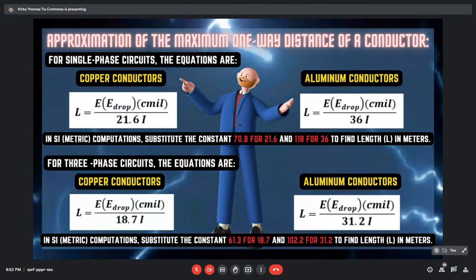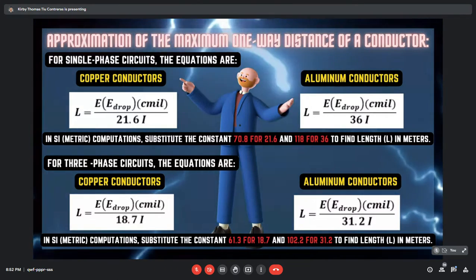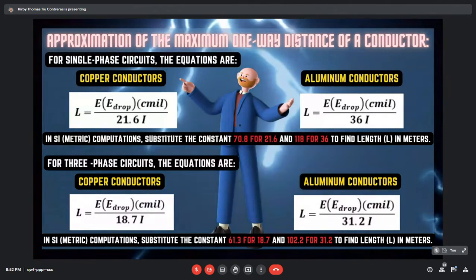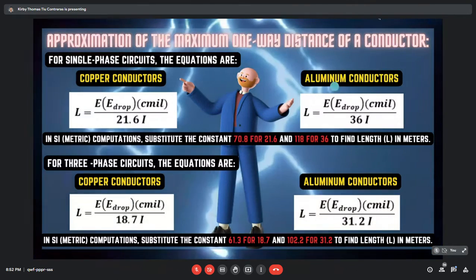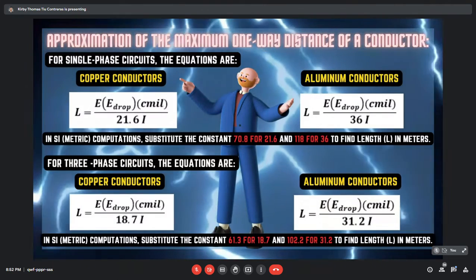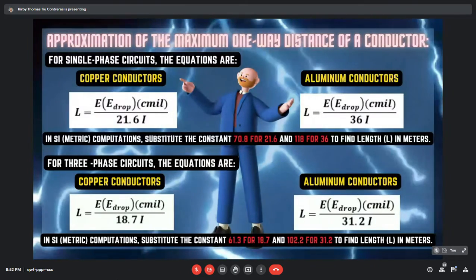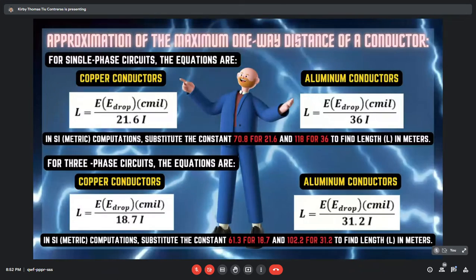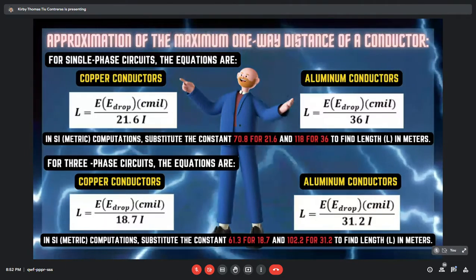And then for three-phase circuits, the equation for copper conductors: L is equal to E times voltage drop times circular mils divided by 18.7 times I, and for aluminum conductors, L is equal to E times voltage drop times circular mils divided by 31.2 times I. In metric computation, substitute the constants 61.3 and 102.2 for the 18.7 and the 31.2 respectively, to get the length in meters.